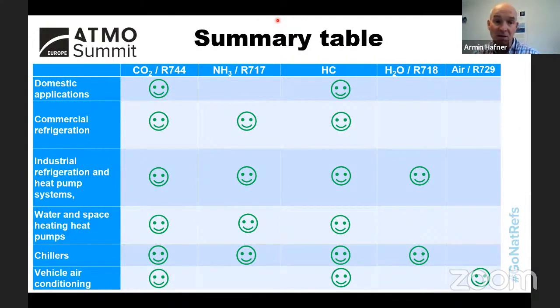commercial refrigeration. When it comes to industrial refrigeration and heat pumps, all except maybe there is no air heat pump system in that respect, but I would say we have large industrial CO2, ammonia, hydrocarbon, and even water systems which are applicable. And water and space heating heat pumps are also possible with CO2, low charge ammonia, and hydrocarbons, of course. Chillers, similar to industrial refrigeration, we can build this kind of system with all natural working fluids. Even car and vehicle air conditioning is done with CO2 nowadays. Hydrocarbons are there, and air in some cases for trains and airplanes.